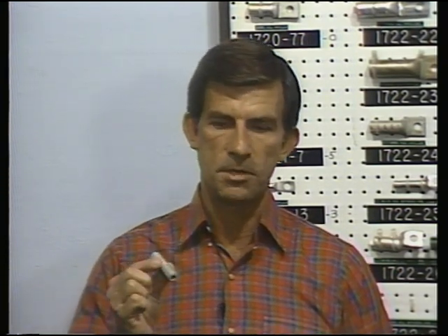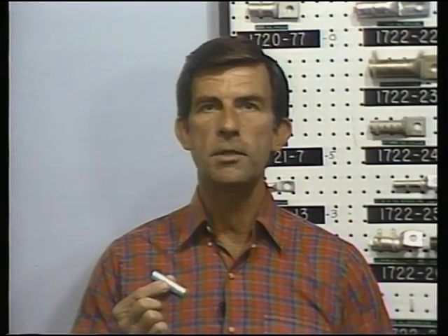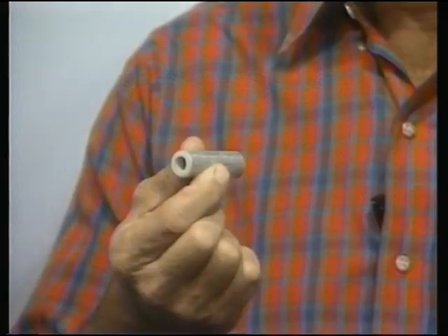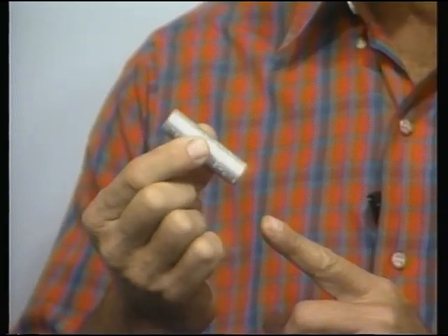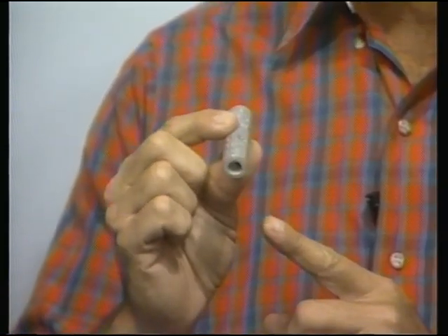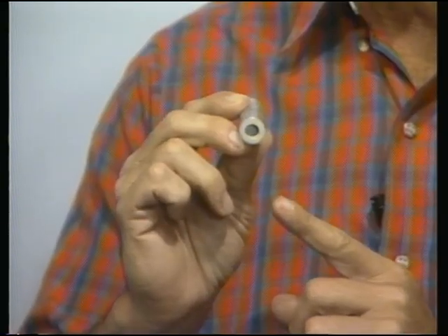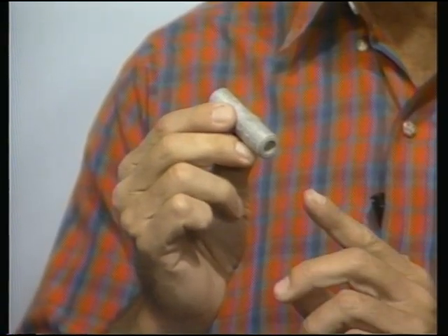In the last segment of the program, we watched the preparations for a tape splice on a single conductor jacketed primary cable. Now, in this part of the program, we'll see the same workman as he completes the tape splice. One of the first steps in making a splice is joining the conductor ends with the connector, sometimes called a sleeve. The connector fits over the ends of the conductors, and high-pressure tools are used to squeeze the connector on at both ends, bonding it to the conductor.